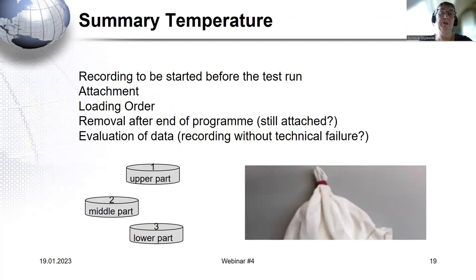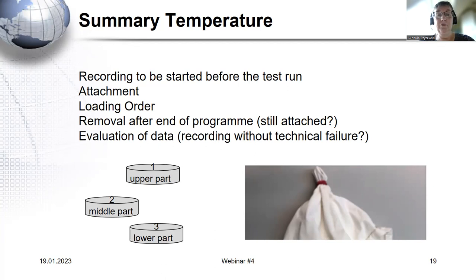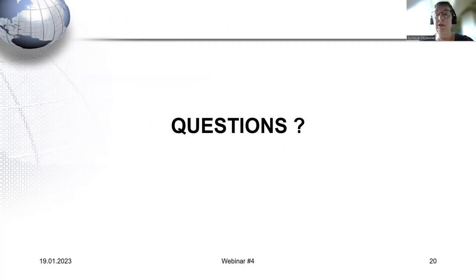Summary for temperature: recording with the data logger has to be started before the test run. Make sure to do a good attachment, stay with the loading order, and check after the end of the program if the data logger is still attached. Have a closer look at the evaluation of the data — is the recording without technical failure, meaning there is no recording stop before the end of the main wash? That's all I wanted to explain here today. If there are any questions about the temperature measurement, feel free to ask.